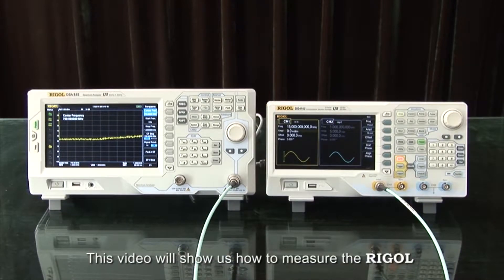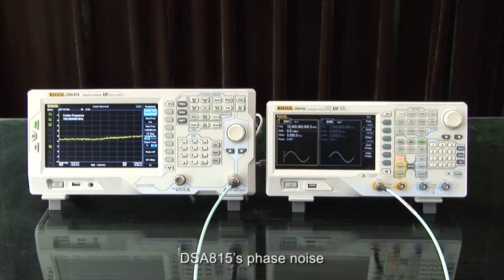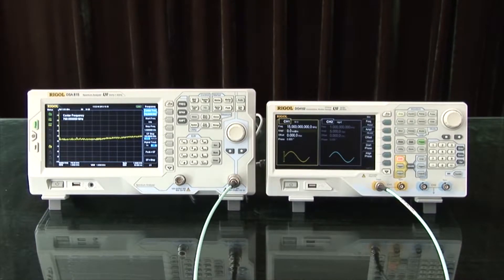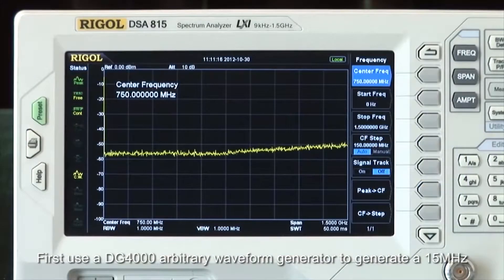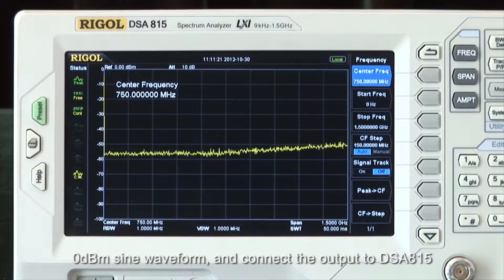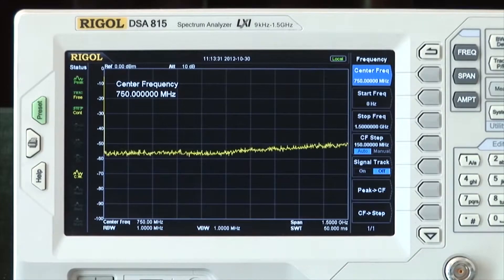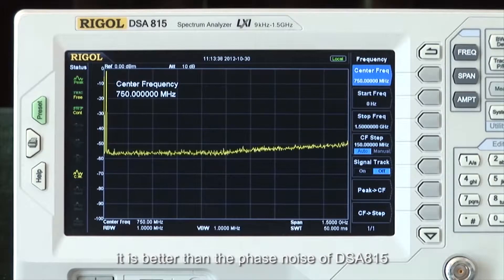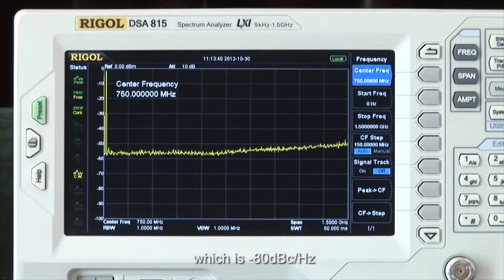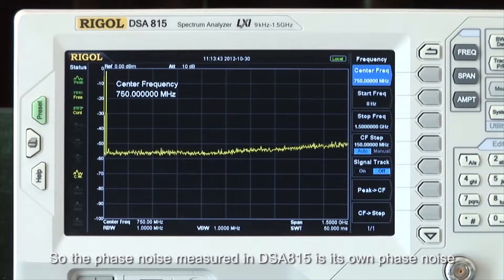This video will show us how to measure the Rigol DSA815 phase noise. First, use a DG4000 arbitrary waveform generator to generate a 15 MHz, 0 dBm sine waveform and connect the output to the DSA815. Since the phase noise of the DG4000 is −115 dBc per hertz, it is better than the phase noise of the DSA815, which is −80 dBc per hertz. So the phase noise measured on the DSA815 is its own phase noise.